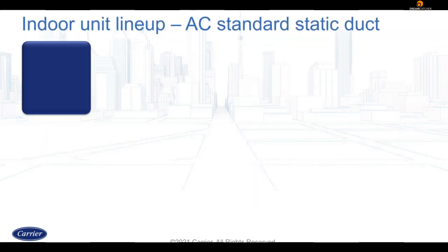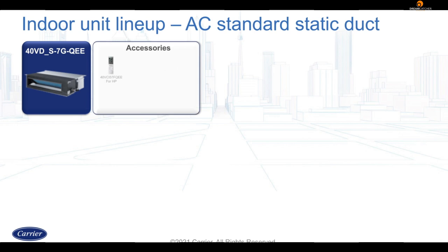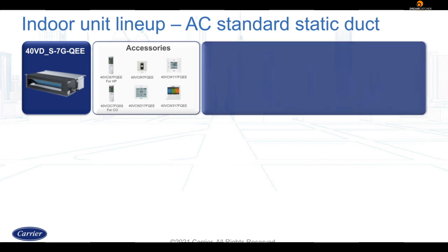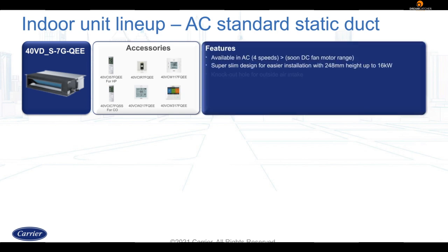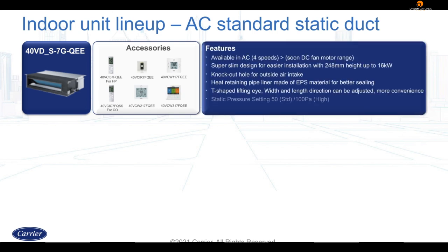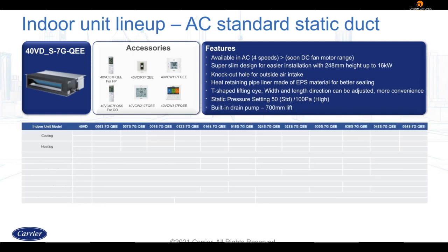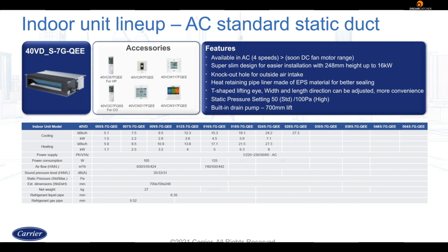The AC standard static duct comes with options of 4 AC fan speeds. Other features are similar to the DC standard static duct, but it has a static pressure setting of 50 and 100 PA for standard and high installations. Recommendations should be made after checking the static pressure requirements of the installation. It also comes with a built-in drain pump of 700 mm lift.